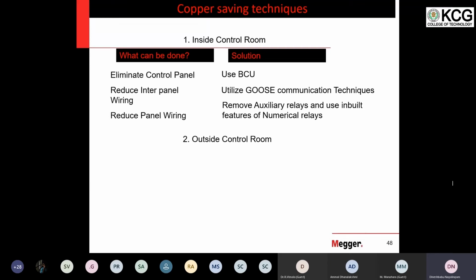But the earth switch is in panel 1, and the breaker is in panel 2. Now how do we communicate? So the status of the earth switch has to be wired to panel 2. This is called interpanel wiring. It's just an example of interpanel wiring. Like this, a huge amount of wiring will be there. Maybe hundreds of cables between panel 1 and panel 2, panel 2 and panel 3, etc. So when we reduce all these things, the panel becomes compact.